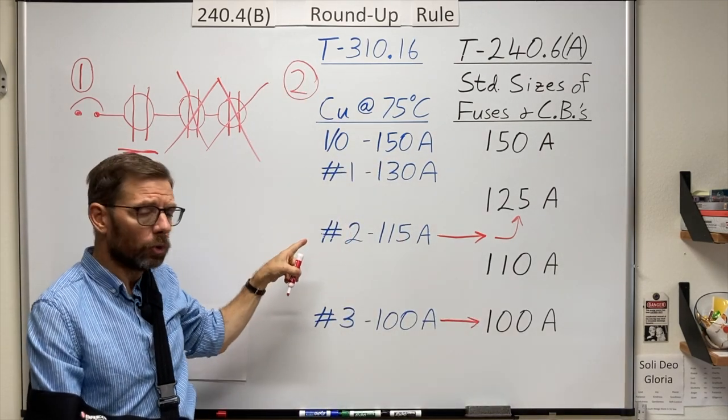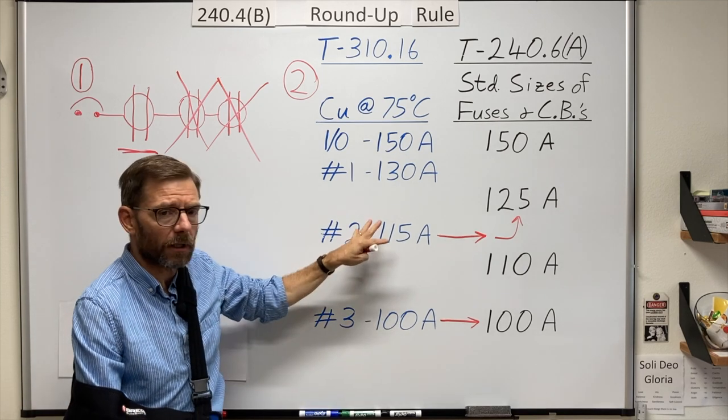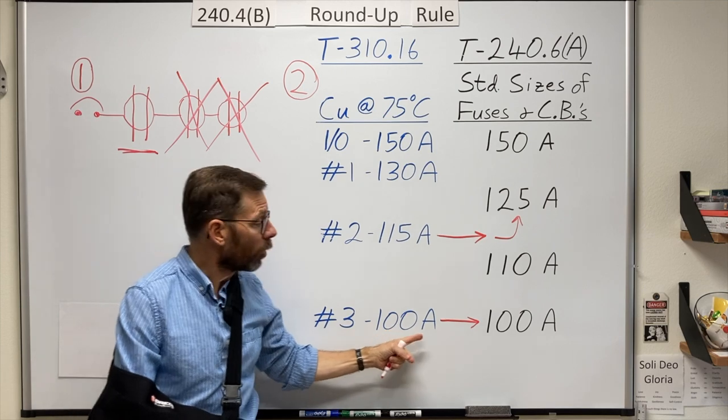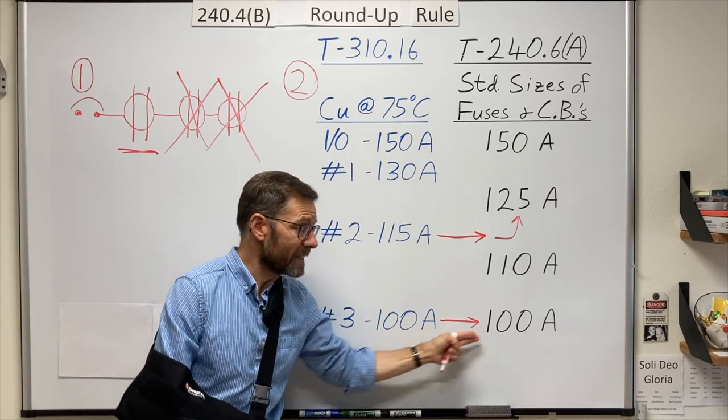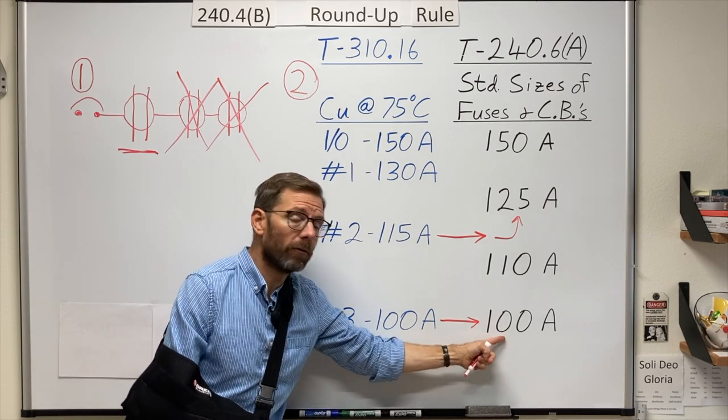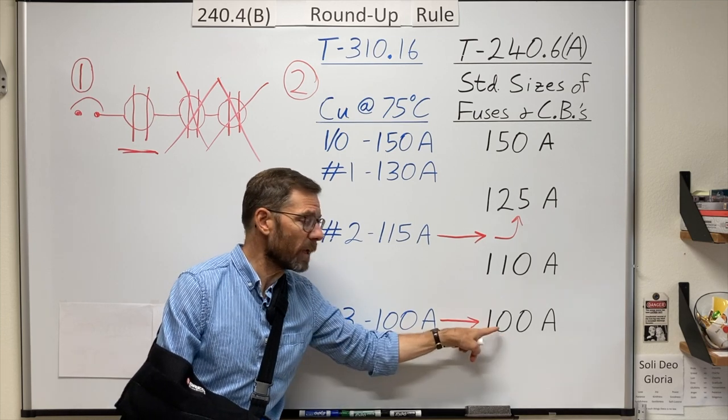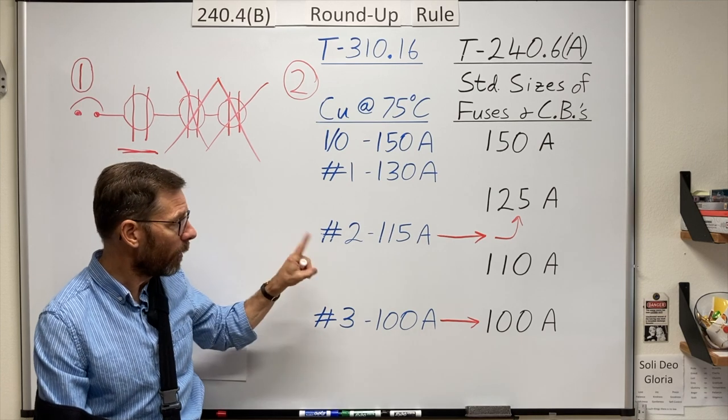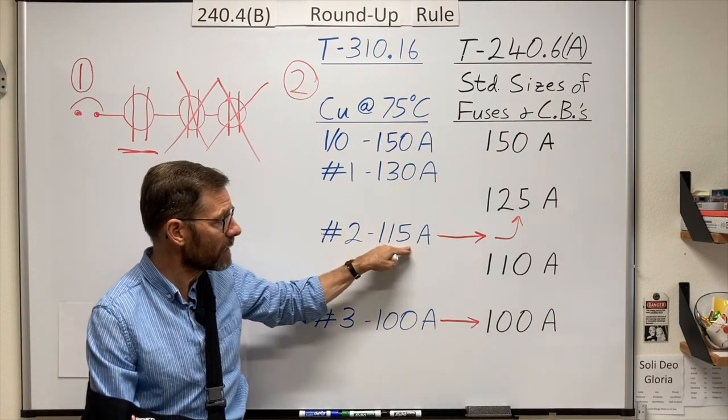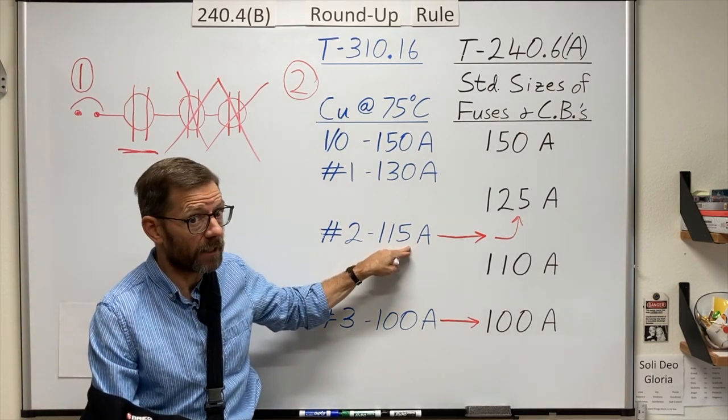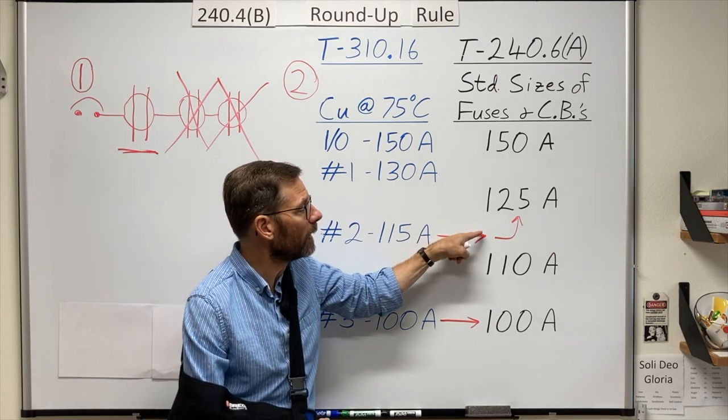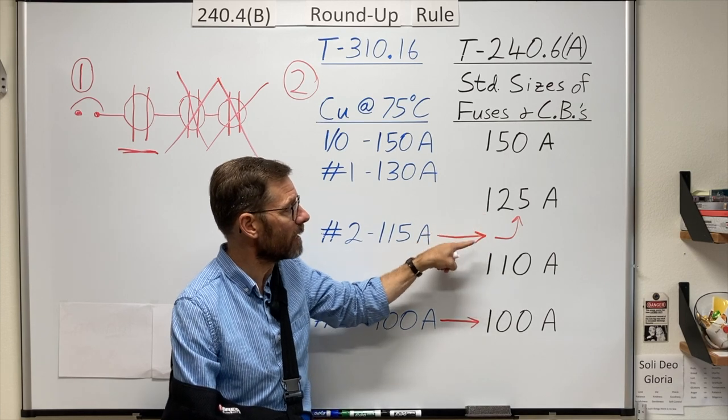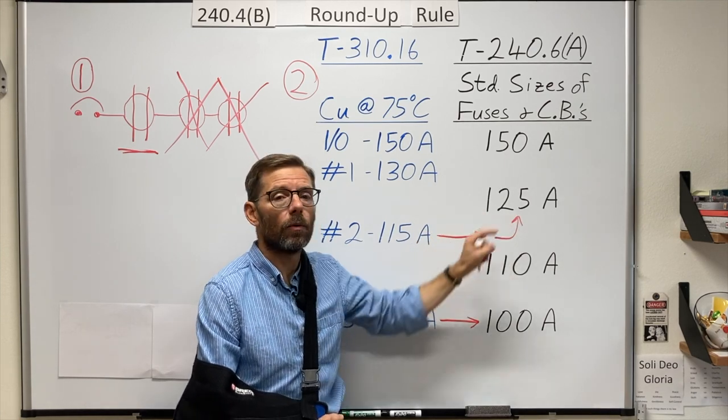Condition number two is largely what we've been talking about here. And it tells me that if a conductor's ampacity corresponds to, or exactly matches, an overcurrent device standard size, then that's what I'm stuck with. That would be the max for this number three. However, if that conductor's ampacity, like I said earlier, after any derating, comes in between, it does not correspond to a standard size, then I can protect it with the next bigger.